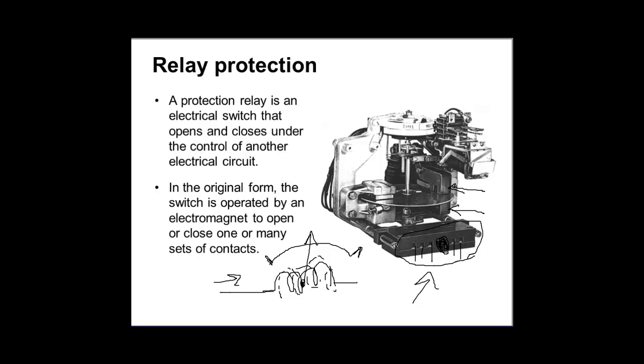When the relay disk starts to rotate, then what? See this shaft? Okay, this shaft will move. Previously this shaft was connected to a needle and we could have some reading for current. But it's not a meter, it's not a galvanometer, it's not an ammeter, it's a relay, it's a current relay. So what will happen? See these contacts, auxiliary contacts? When the disk starts to move, that shaft or gear will start to move, and those auxiliary contacts will change position from on to off or off to on.